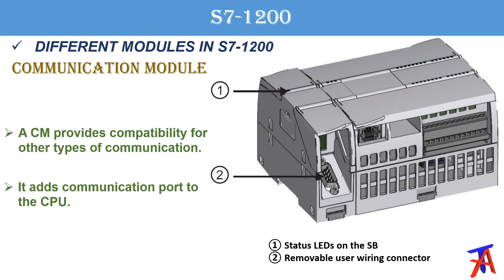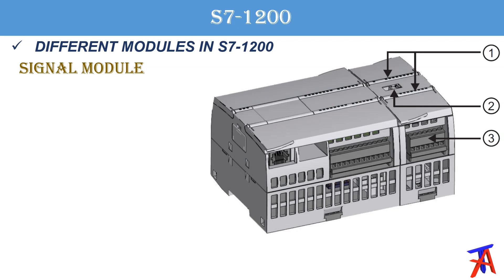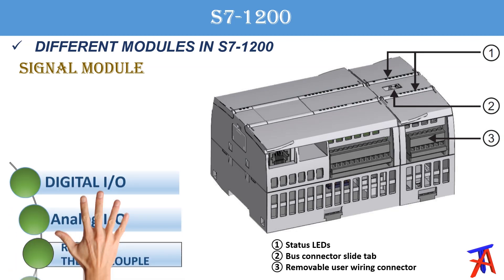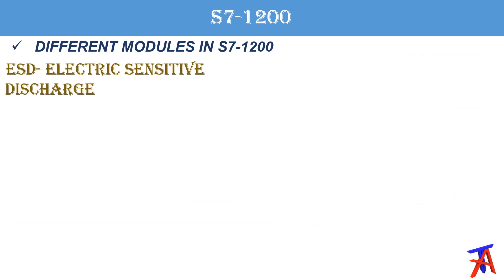The communication module provides an additional communication port not available on the PLC by default. Next are signal modules, which can be added to the right side of the PLC. Signal modules can be of various types: digital inputs or outputs, analog inputs or outputs, RTD and thermocouple temperature sensors, and SM1278 IO-Link master.